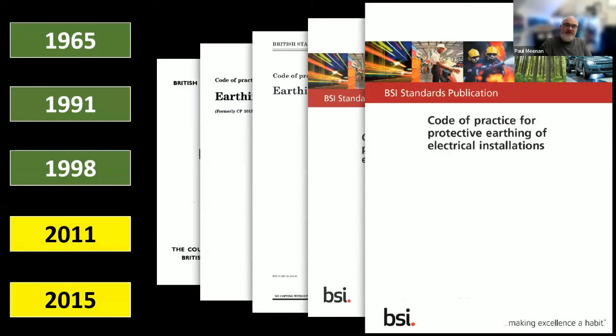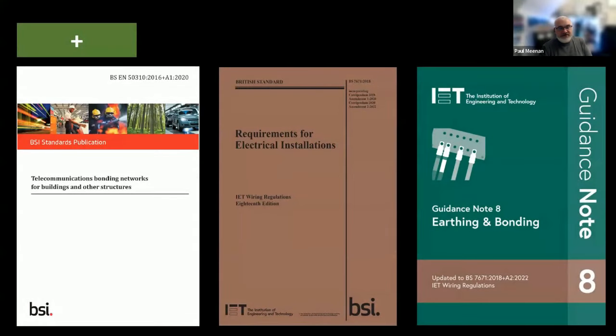So a lot of the HV engineers, a lot of the lightning protection engineers, a lot of the earthing specialists, this is their book. This is what they use a lot of. But as good engineers, we shouldn't just limit ourselves to one standard. That we will make mistakes. We need to consider the guidance in other very well-educated publications from experts. So you look at BSEN 50310, which is telecoms bonding for buildings. You know, if you have data centers, a very important standard. We have guidance in Chapter 54 of BS 7671, which relates to the IEC standards. We have guidance notes specifically just on earthing and bonding.